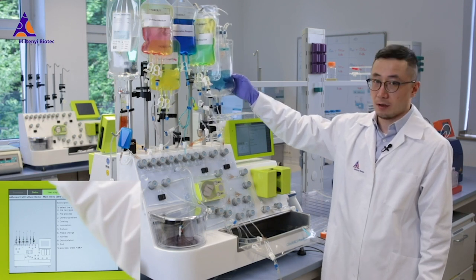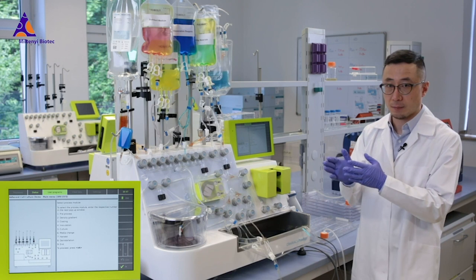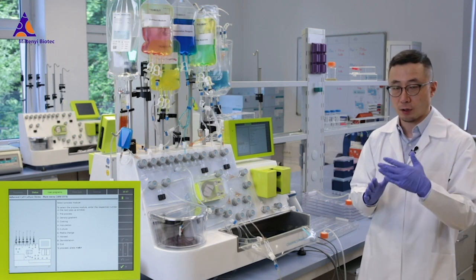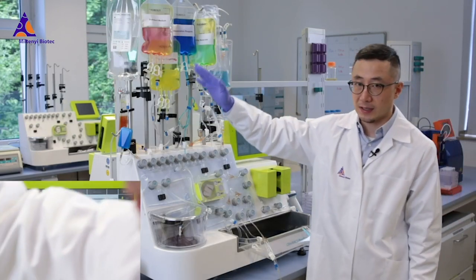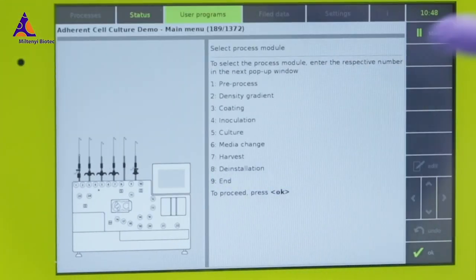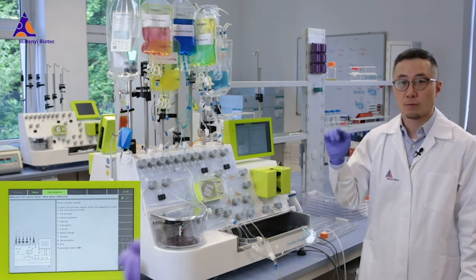After harvesting, if we combine the harvest module with the inoculation module, we can replate the harvested cells into new cell culture vessels — basically splitting and passaging the cells to continue cell culture. This is how we combine different modules and use them in different ways for different purposes. If the cell manufacturing process is finished, we use module number 8 — de-installation — to de-install the tubing set from the CliniMACS Prodigy device, following the instructions on screen. Then module number 9 finalizes the manufacturing process and you can export the log file from the Prodigy system for your recording.